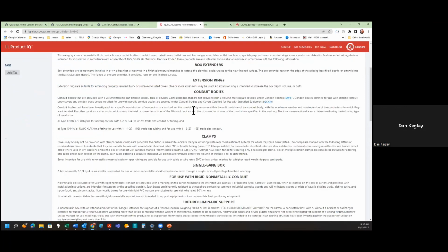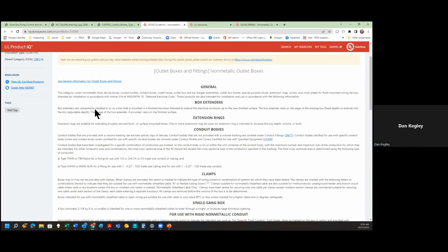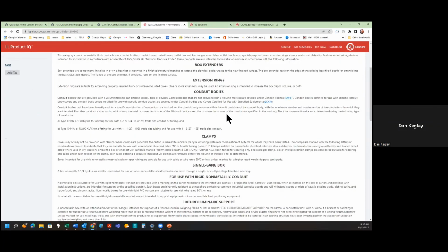So if it's a box extender, extensions, but we're dealing with conduit bodies. So then it goes into the details or the specifics of the conduit body and what it's tested for and what it can be used for. Like in this particular case, it says the total cross-sectional area of the fill should not exceed the cross-sectional area of the conductor specified in the markings. So inside the LB, it'll say no more than 3 4-aught conductors for a 2-inch LB.